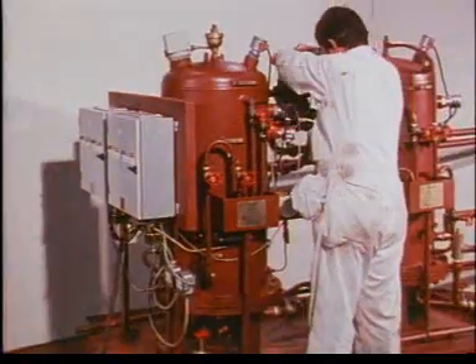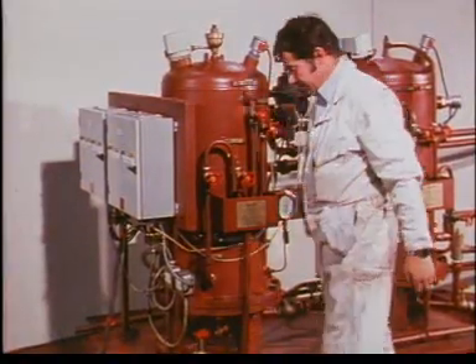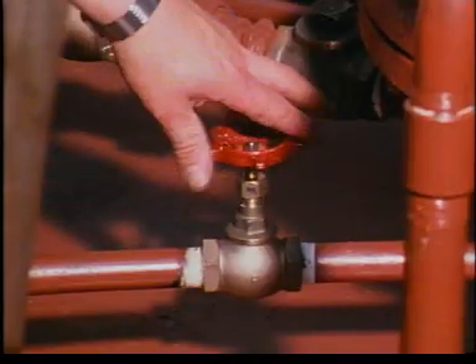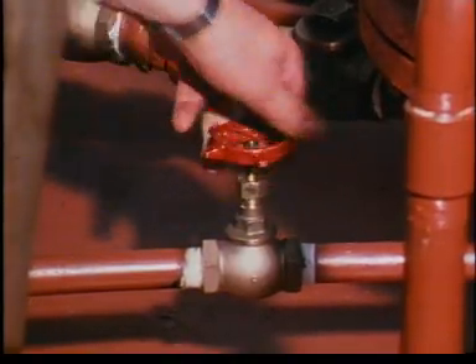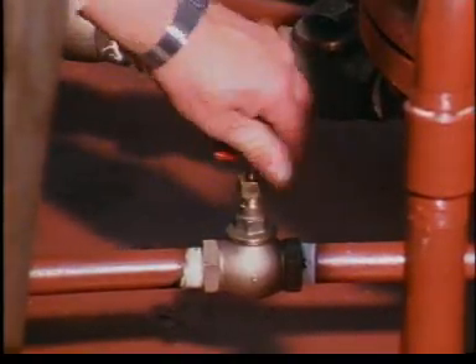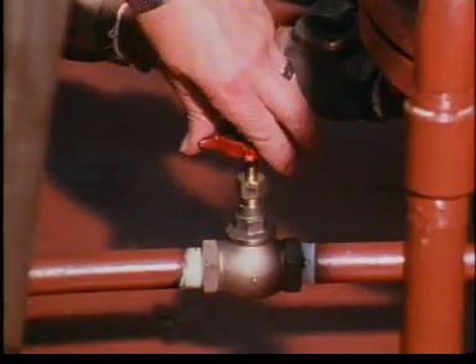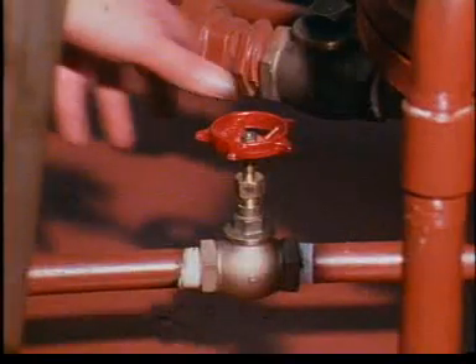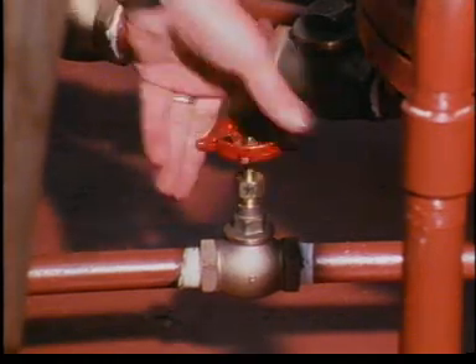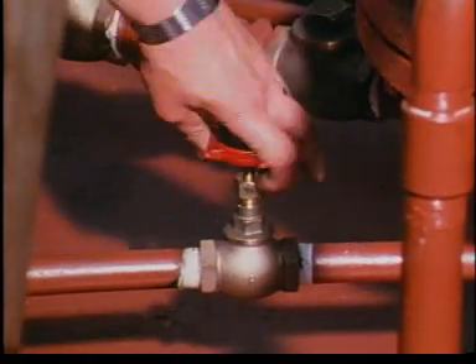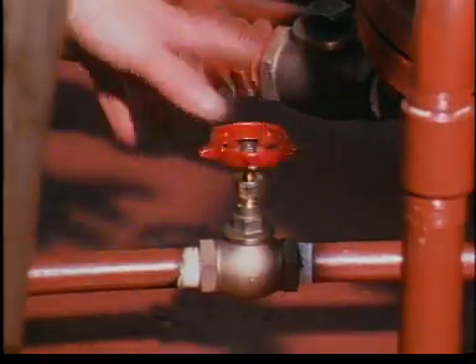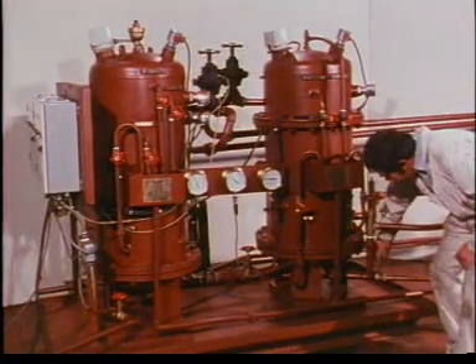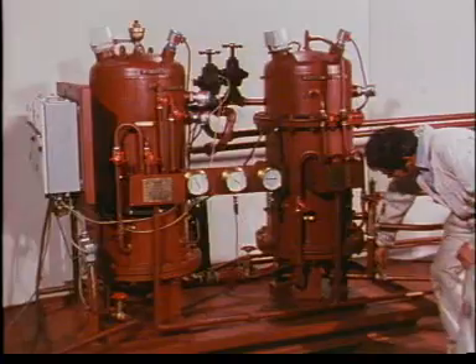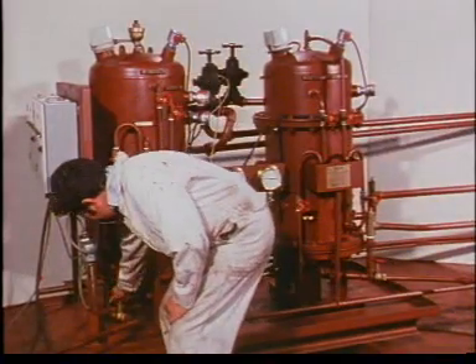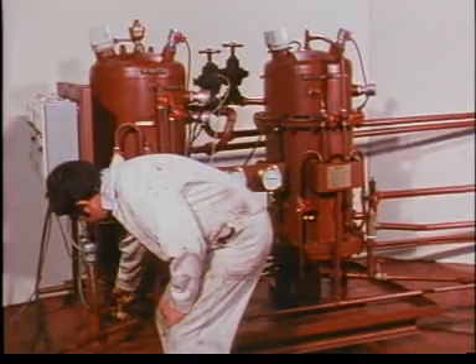Now, while continuing to pump clean water through the system, the drain valves on both stage 1 and stage 2 are opened. Pumping of clean water through the system is continued for a short while. After this, the two drain valves are closed again. The filling valve can now be closed and the system left full of clean water. This prevents internal turbulence when restarting the plant and reduces corrosion when the plant is idle.